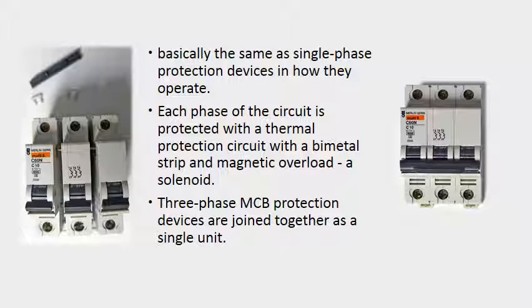So three-phase circuit breakers are basically the same as single-phase circuit breakers. They have the same protection for each phase, but there's three of them. Each phase is protected with a thermal protection circuit which has a bimetal strip, and it also has a magnetic overload with a solenoid. They're joined together as a single unit, and if you have a look here in this photo, there's a tripping mechanism which is common to all three.